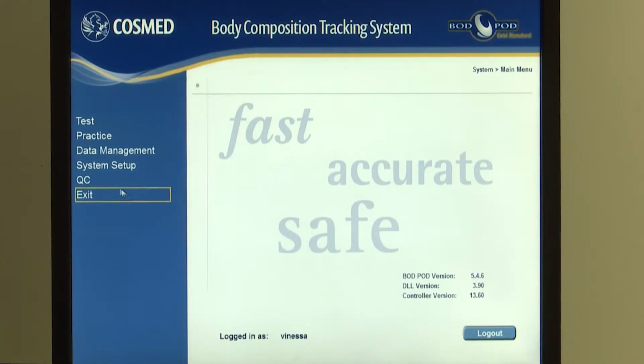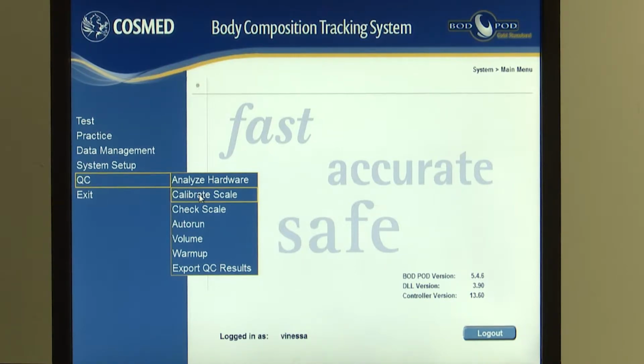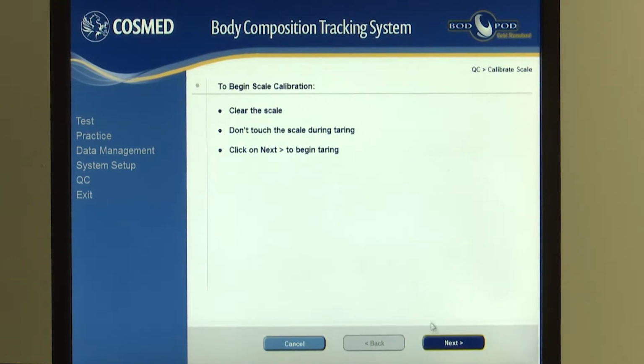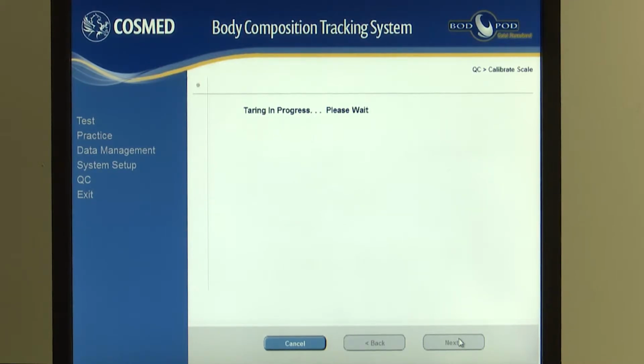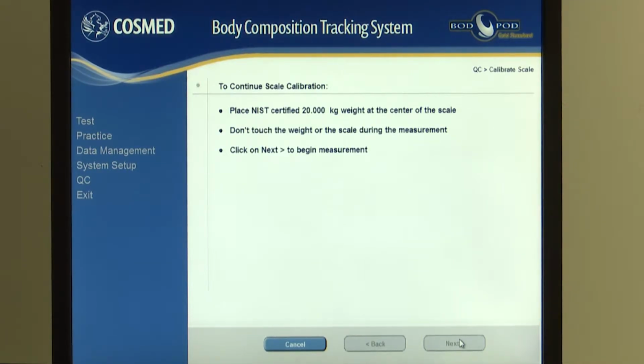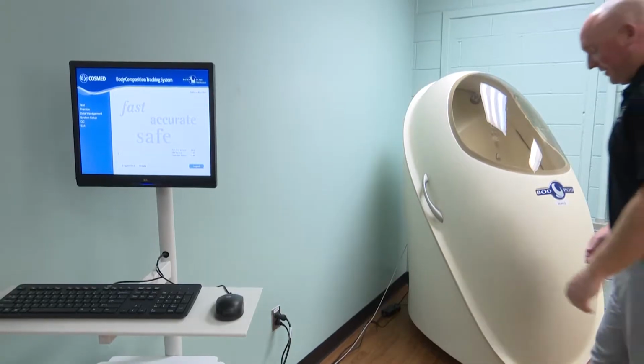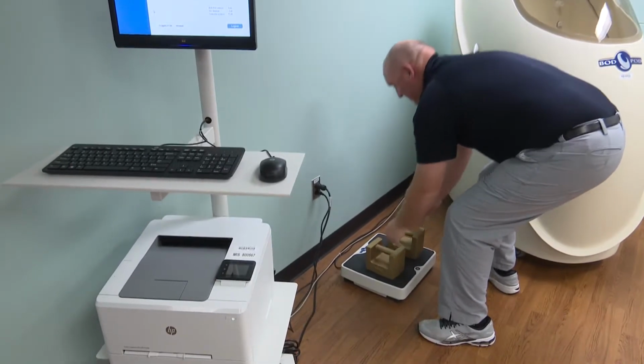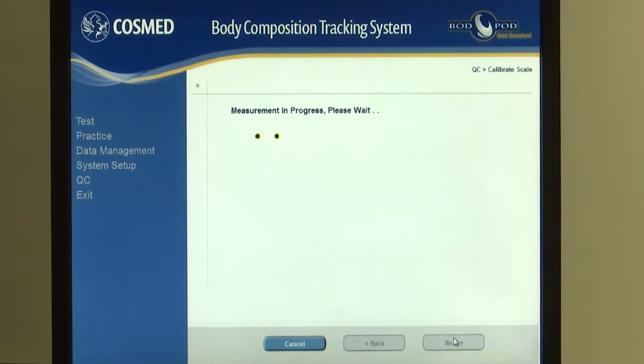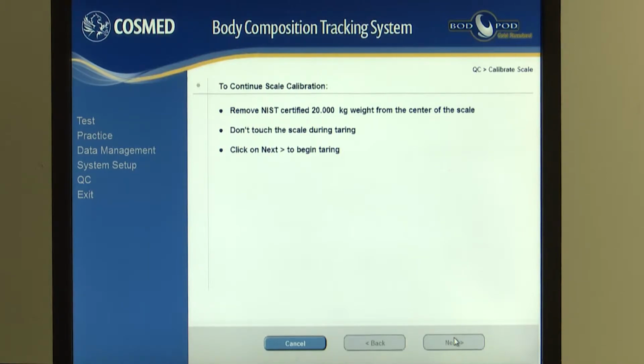Go back to the QC tab, open the drop-down menu, and click Calibrate Scale. Follow the prompts on the Bod Pod screen. The software calibrates the empty scale to give it a beginning value and makes sure it is level and no additional weight has been put on the scale, which will skew the weight results. Once that is complete, the 20 kilogram weights are placed on the scale. This is a known value for the software and allows for an accurate calibration of the scale. The software will then calibrate the weights on the scale. The software requires the weights to be placed on the scale and removed 3 times until a complete calibration of the scale has been done.